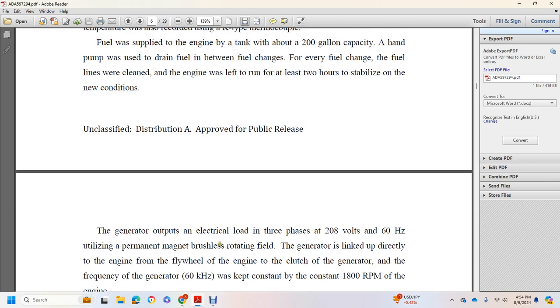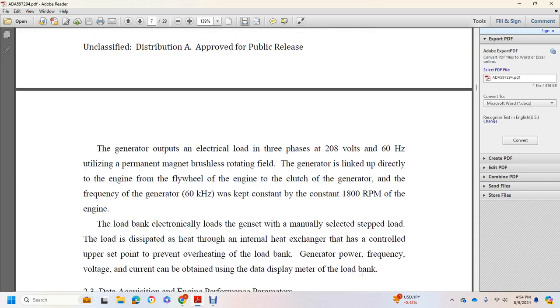The generator outputs electrical load with three-phase at 208 volts and 60 hertz, utilizing a permanent magnet brushless rotating field. The generator is linked directly to the engine flywheel. The generator frequency of 60 hertz was kept constant with 1800 RPM for the engine. The load bank electronically loads the generator set with a manually selected step load. The load was dissipated as heat, and the internal heat exchanger was controlled by an upper set point to prevent overheating of the load bank.